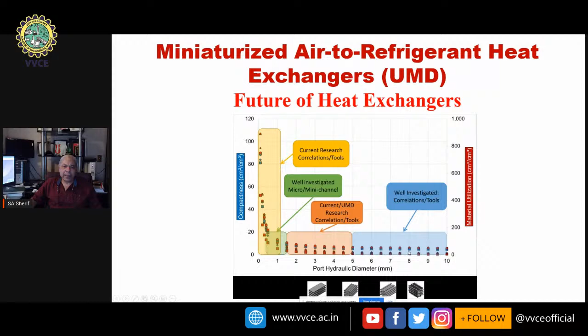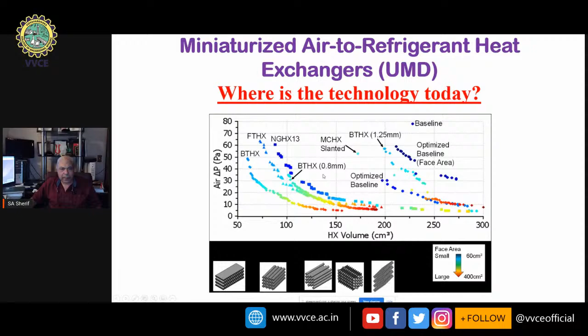This is another picture showing the different types of heat exchangers you can use to achieve that. This shows the heat exchanger volume and the pressure drop associated with each technology. Remember, in heat exchanger technology, your objective is not just to maximize heat transfer, but to also minimize the pressure drop, with minimal power consumption.